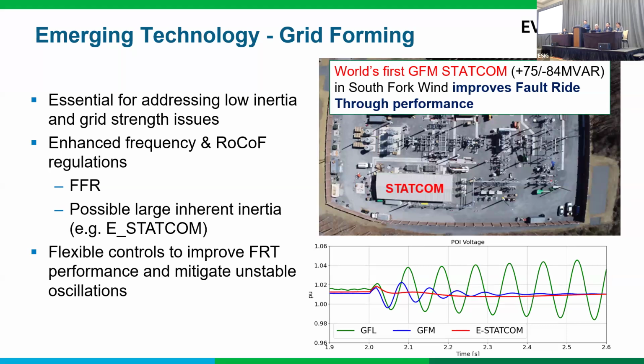South Fork Wind installed a grid forming STATCOM in order to improve the stability and the ride-through performance, because South Fork Wind actually connects to a weak grid. Unfortunately, most offshore wind in the US connects to the weak grid on the East Coast. The performance of the STATCOM has been validated and approved in the conventional tests, the stable voltage test and stable frequency test, and we compared the recorded data with the simulations. So this device works as designed. Ideally, the eSTATCOM would be even better.